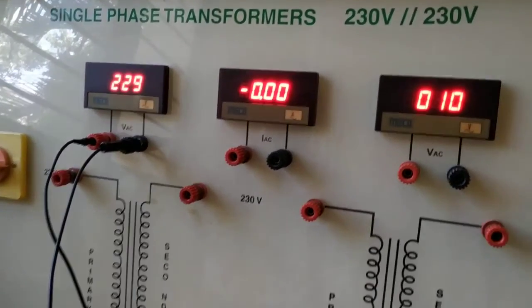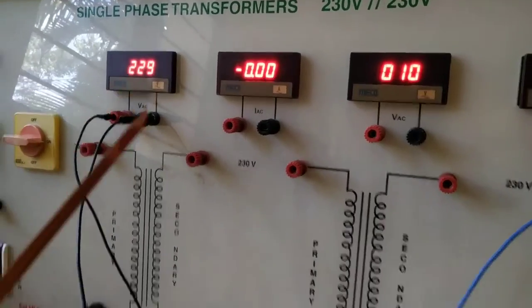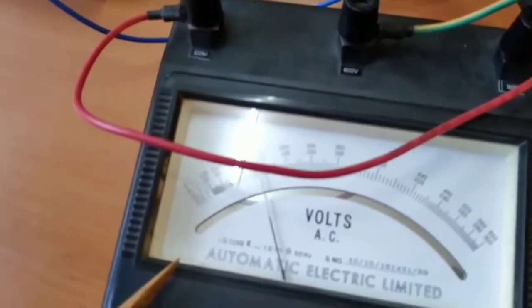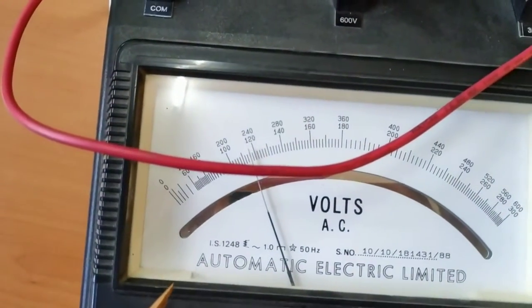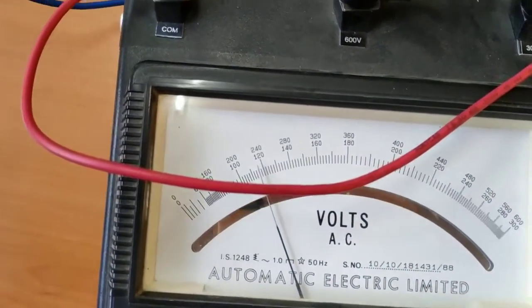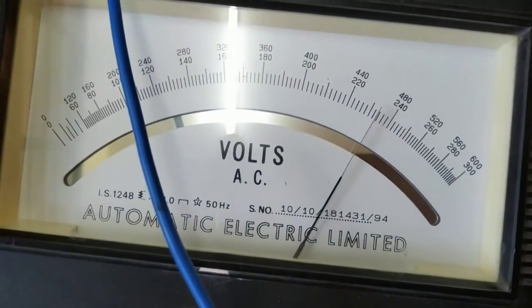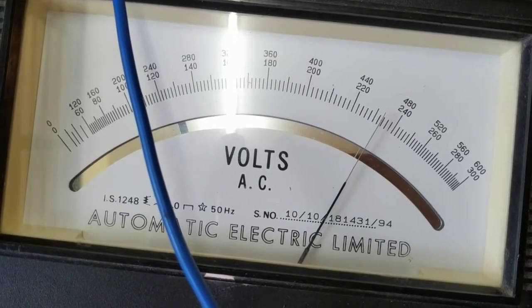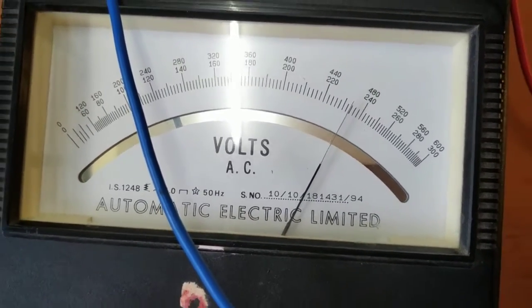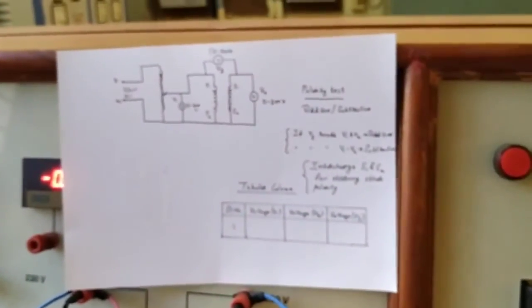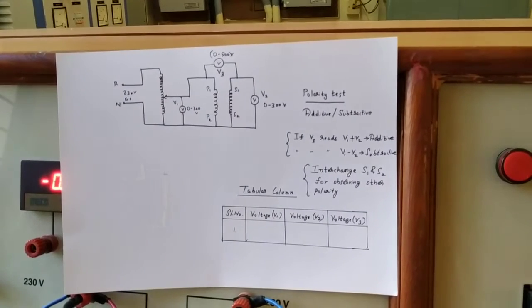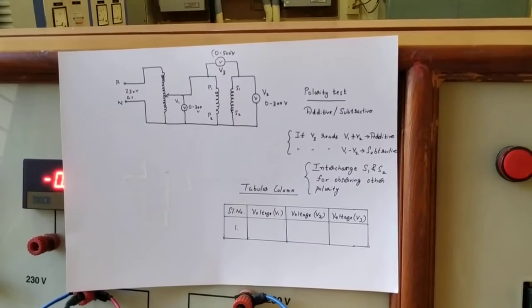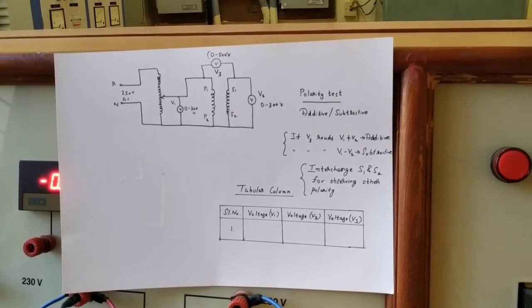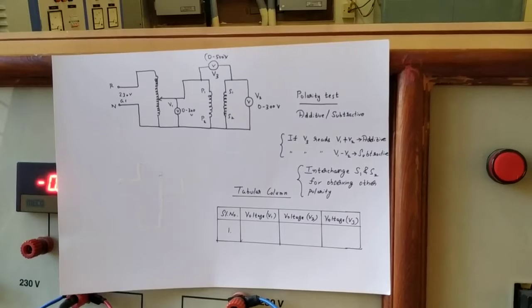Now we can clearly observe that V1 reads 230 volts and the voltmeter across the secondary also reads 230 volts, as this is a 1:1 transformer. Now you can observe the reading on voltmeter V3, which is almost equal to 460, which is the sum of V1 and V2. So this represents additive polarity. Before doing the parallel operation of transformers, first we have to check the polarity, and before doing the load test we also have to check the polarity. This is the procedure by which you check whether it is additive or subtractive polarity.